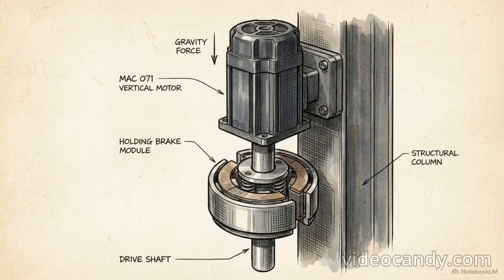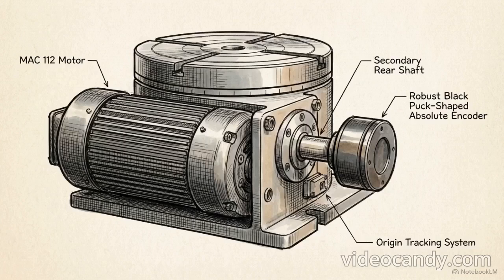Looking back at the schematic of the multi-axis machine tool, it becomes clear that no single motor type can satisfy every axis requirement simultaneously. For a vertical Z-axis, an engineer specifies a MAC 071 motor outfitted with a closed-circuit holding brake. Because gravity constantly acts on the vertical column, the holding brake is necessary to clamp the output shaft and prevent the tooling from dropping during a sudden power loss.